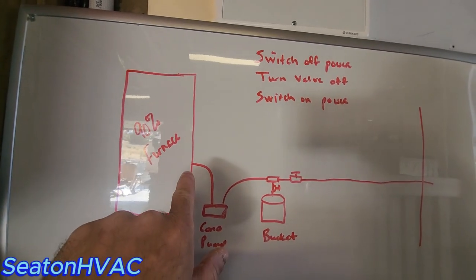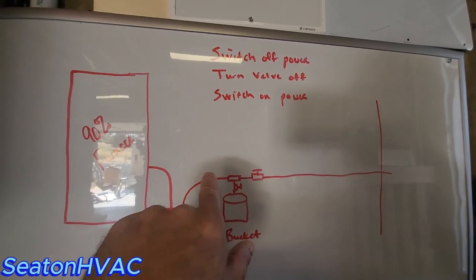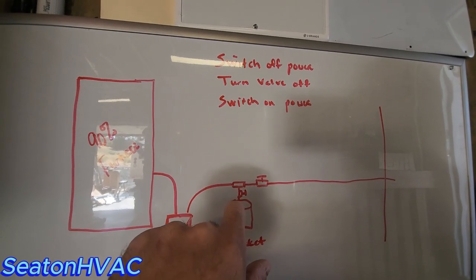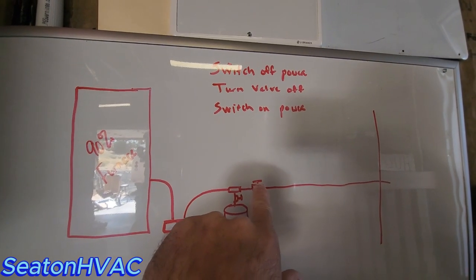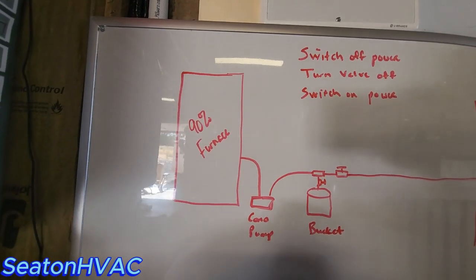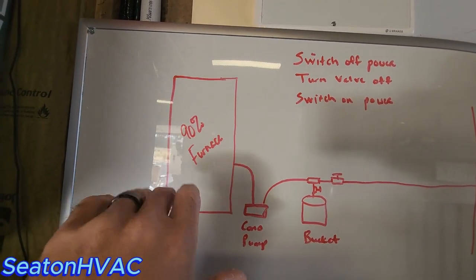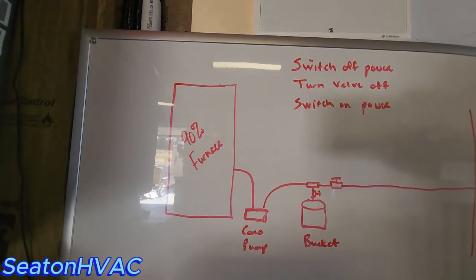Same scenario if you had just a PVC drain going all the way out - you could tee it, put a valve going down into a bucket, and a valve going outside. You just switch the valves, cycle the power so the error code clears in the furnace, and that'll get their furnace back up and running.